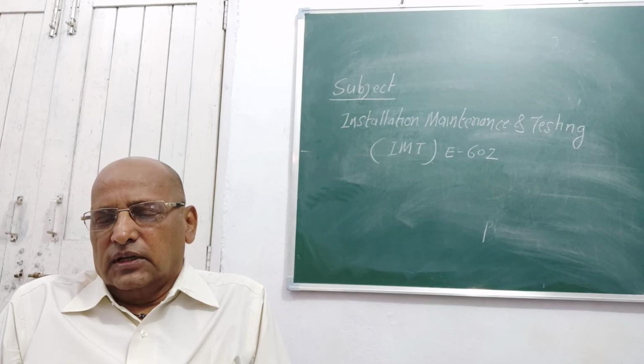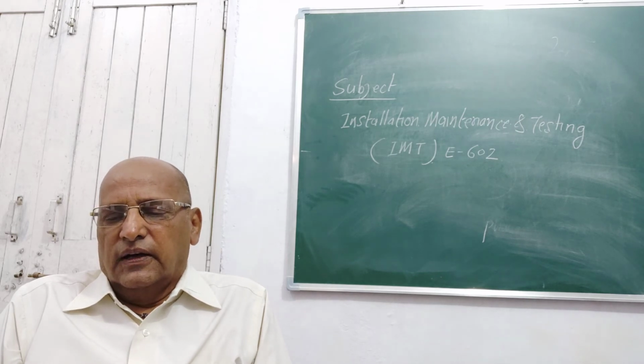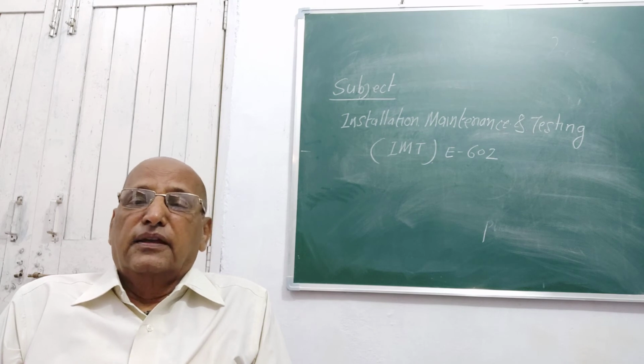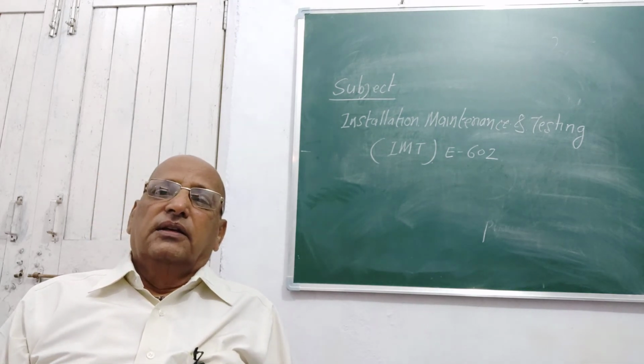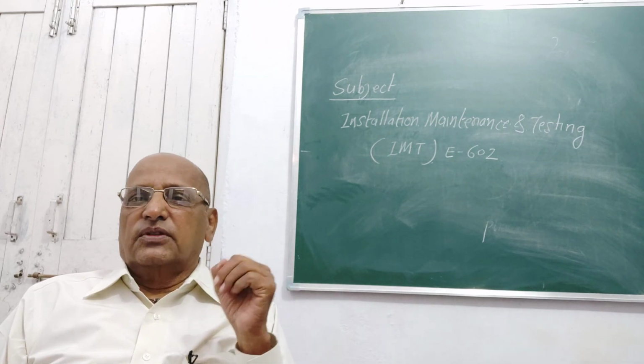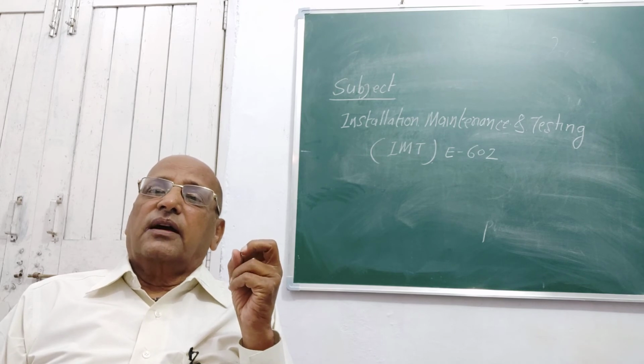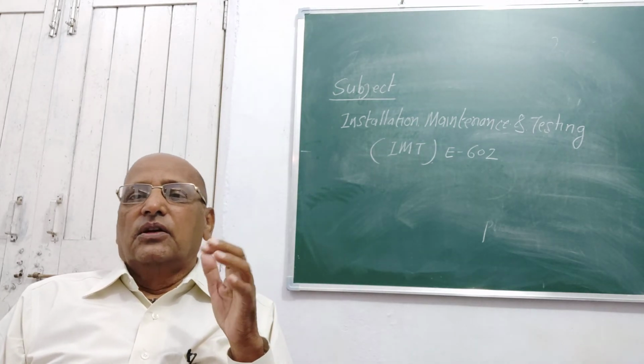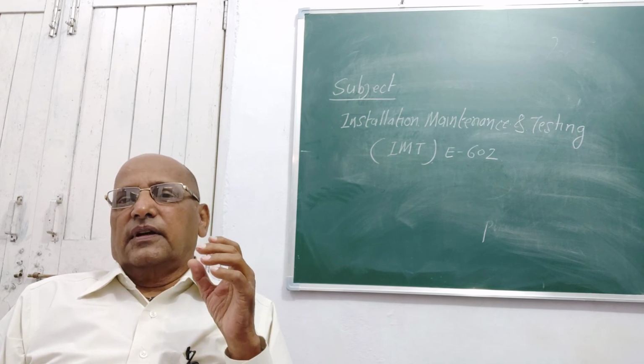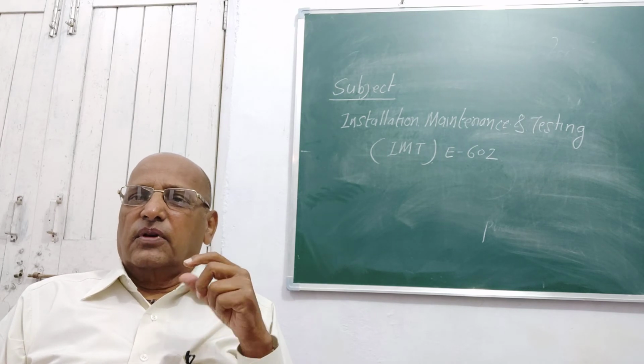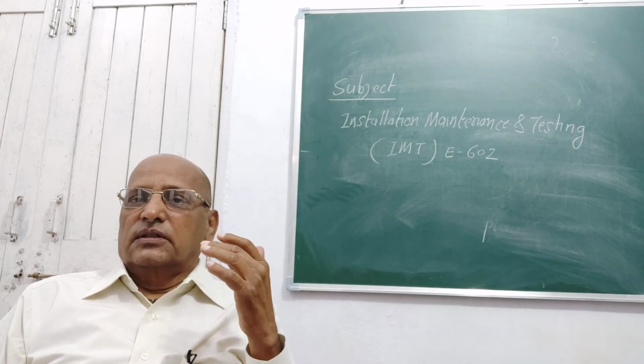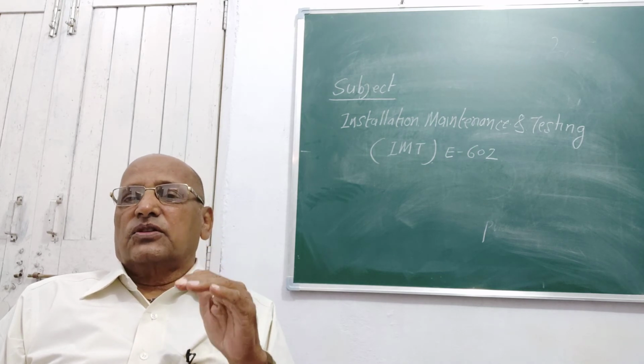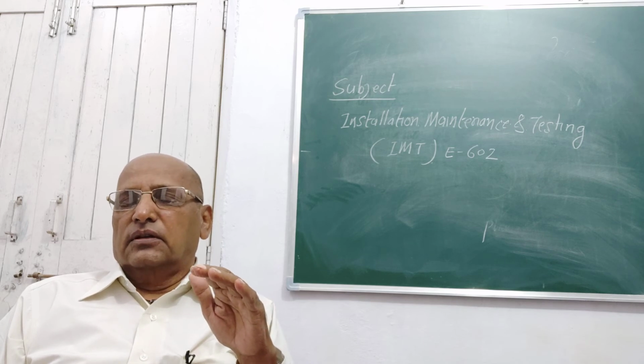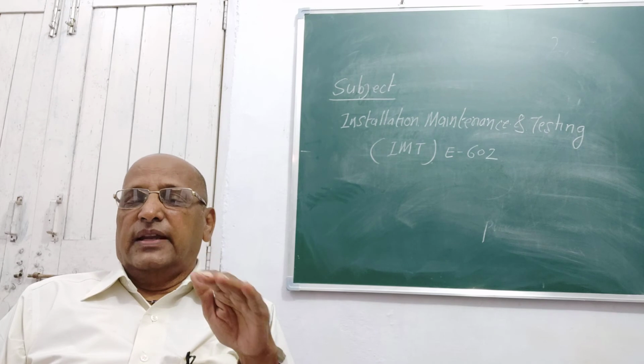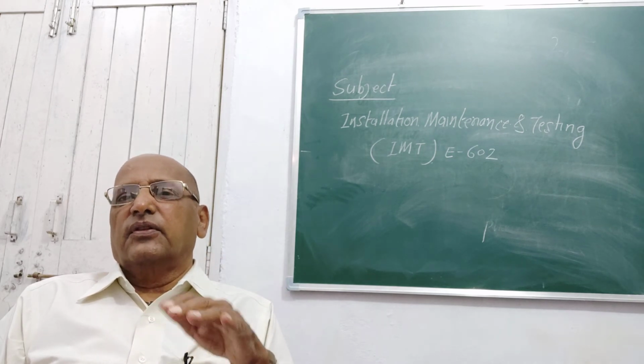So this is all about the installation of the pole mounted transformer. When this type of transformer is to be installed not on a pole but on a foundation, in the case of a multi-storied building, the supply is given by transformers installed on the foundation. These foundations are prepared with a brick structure or a concrete structure, and in this case again we require two poles for the accessories like AB switch, DO fuse and lightning arrestor. But the transformer is not kept on channels, it is kept on the plinth. Plinth means it is a foundation.